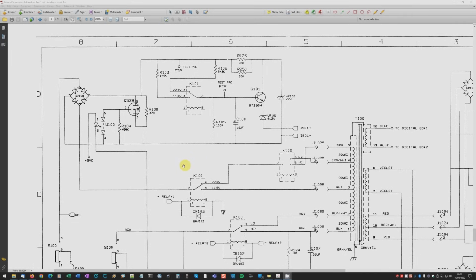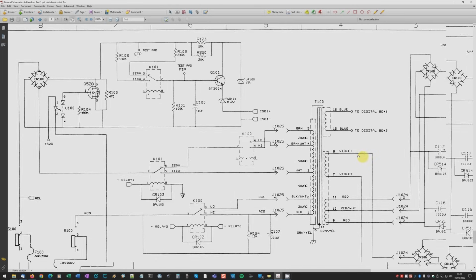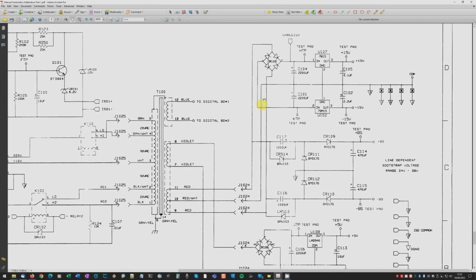So back to the first diagram, here's that 220, 110 volt relay. You can imagine if there's some problem with the signal coming from that other schematic driving this relay, or if there's a problem with the relay itself, you could theoretically have 240 volts coming through on the 110 volt side of this primary winding, and basically over-voltaging the secondary side, which would in turn over-voltage all of these regulators here, the positive and minus 15 and the plus 5 volt regulator and these unregulated supplies.